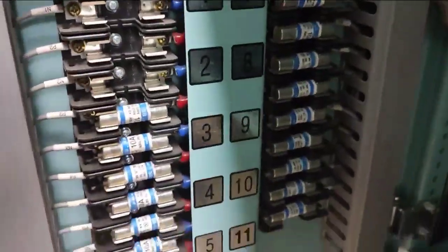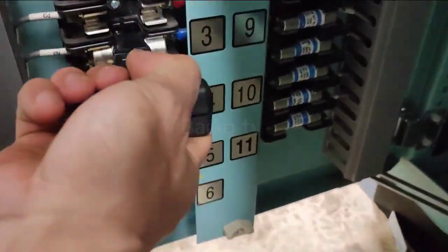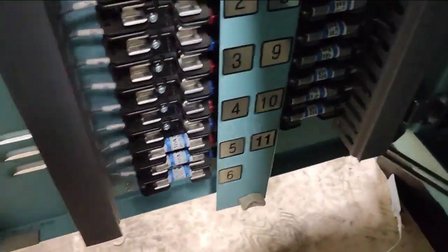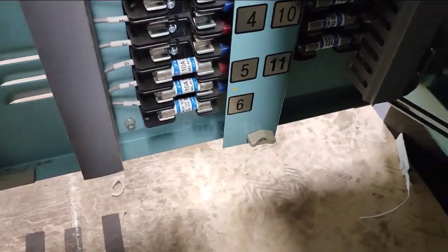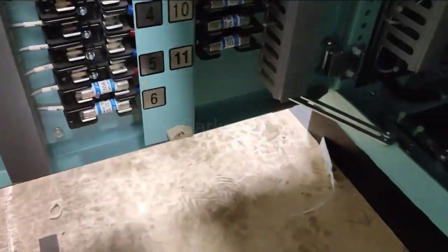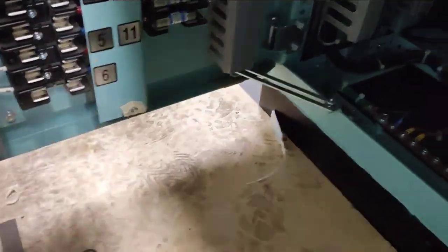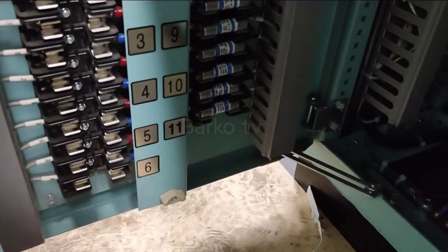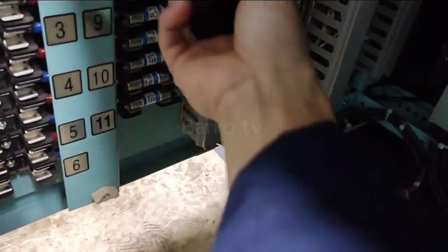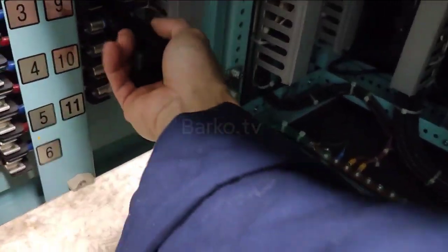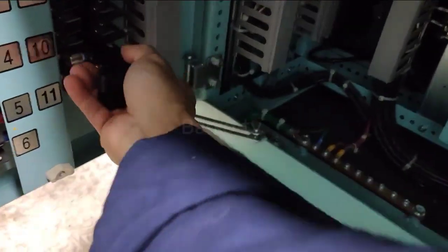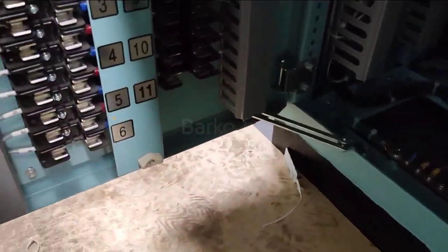This is the fastest and easiest way to locate the ground fault in 24 volts. This is the accurate one. You need to remove all fuses. Because a simple tip: when you remove the fuse and the IR monitor drops, that means that is the fuse that is grounded, or the fuse that supplies the equipment that is grounded.